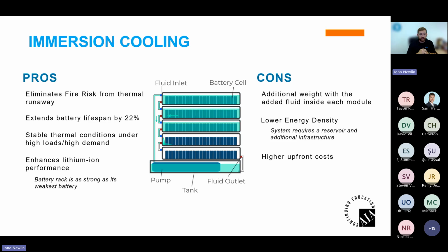Then you also enhance lithium-ion performance. Because you have better cooling, you have a better life cycle - a charge and a discharge. High heat causes degradation to happen quicker, and now with better thermal management, we're able to get better performance out of the batteries.